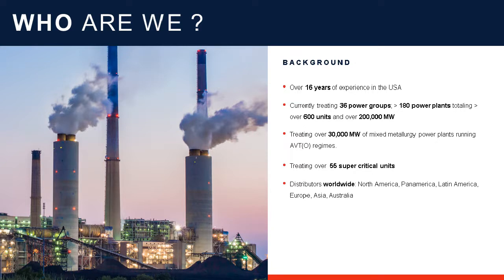The common problems were increase of cation conductivity by decomposition of the amines. They form small organic acids, cyclic molecules like benzene, for example, all those kind of things. And also there is a risk of formation of fatty deposits and so-called gunk balls when overdosing. Then he developed a chemical substance which could solve the negative effects and fulfill all of the requirements of the cycle chemistry. Meanwhile, Anodamine is the benchmark in surface active chemistry in the USA and is now spreading globally.